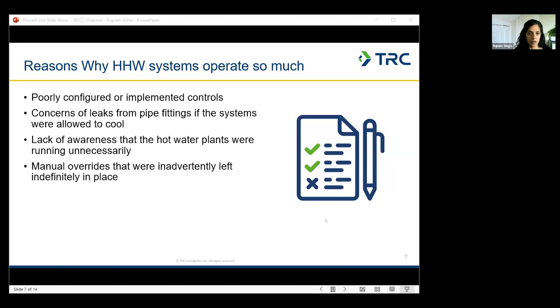Our next finding is around hot water supply temperature. So this figure that I'm showing shows what we expect to see regarding hot water supply temperature. So what we see is that when it's cold outside, the hot water supply temperature is relatively high. It's around 160 degrees. And then as the outside air heats up, as the conditions get warmer, the supply water temperature decreases and gets to a minimum of about 120 degrees.